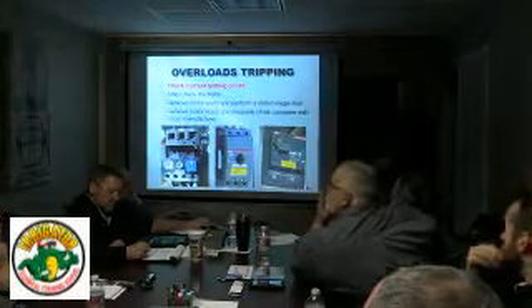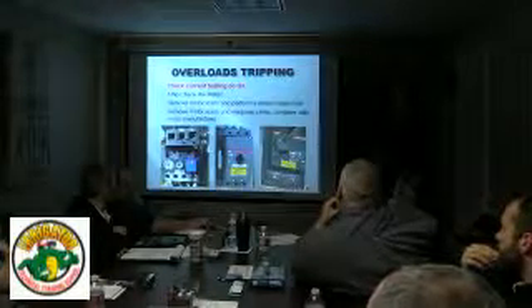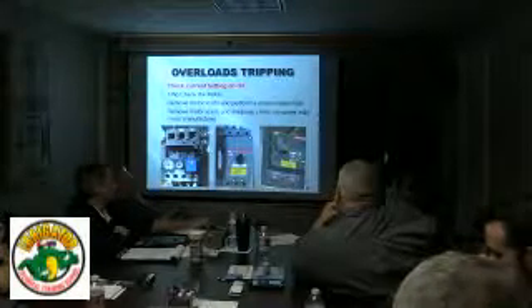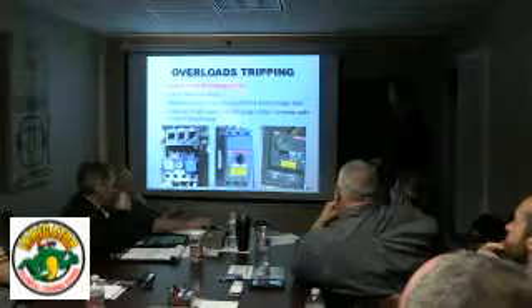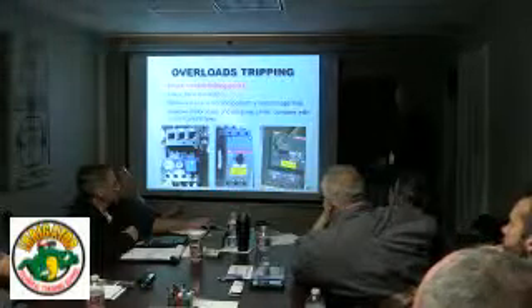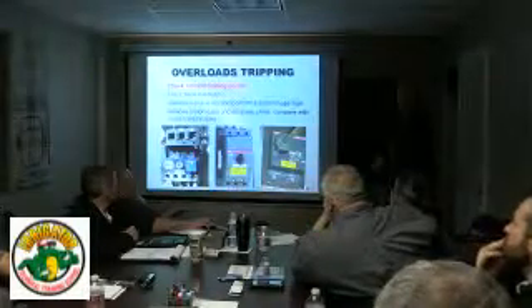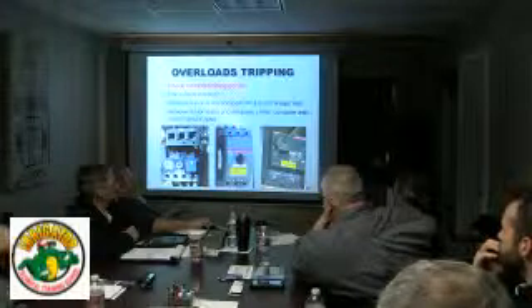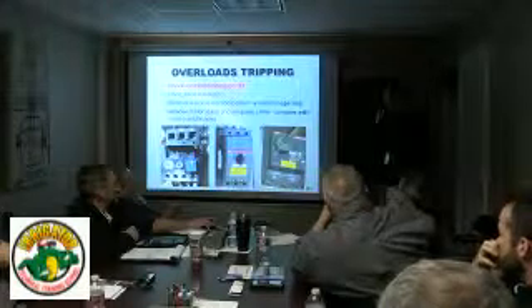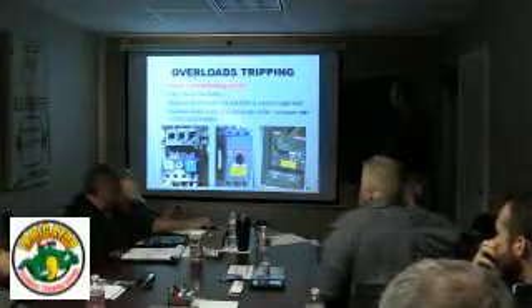This is on some of our bigger systems. This is a main disconnect overload with an overload, but it's also got an instantaneous trip. So keep that in mind if you're looking at it tripping and you want to double check and make sure it's set at the correct amp rating. One of these is going to be the normal amp rating like you would see on any other overload. Look at the rating in our schematics or on the VFD to check that one. The other one, if you look at it closer, it's going to be way over. It's going to be like 200% of normal. That's an instantaneous trip, which means it will trip really fast if you get a high spike. The voltage goes that high that quickly, it'll trip, a lot quicker than this one will. So there's just some of the different kinds of overloads.